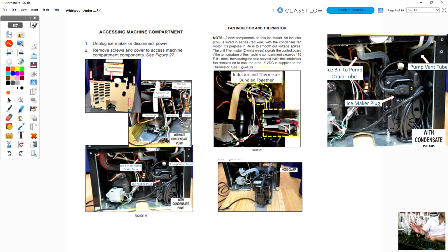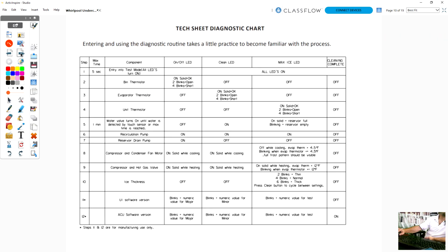At the same time it is doing that to remove the ice, we are also sending voltage to our water valve. Our water valve is calling for water and filling up our reservoir. So our drain pump drains out, and I think the drain pump initiates on the ice ejection cycle to get any remaining water out. Then the water valve will come on, and then the water level sensor will tell it to stop filling with water. Once the water level sensor has reached its mark, it'll stop filling. That does not tell the machine to start producing ice yet, because it's going to work either by the evaporator thermistor or the time limit. The evaporator thermistor is going to tell the unit, I think they said it was 54 degrees. Let me see if I can find that.